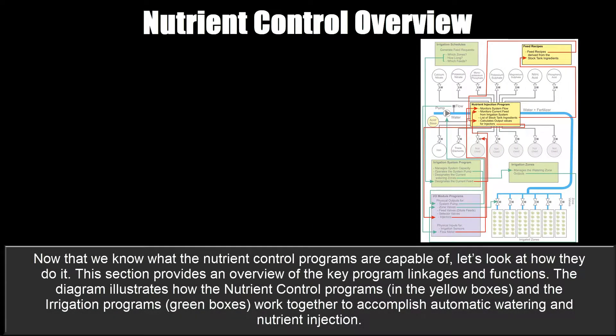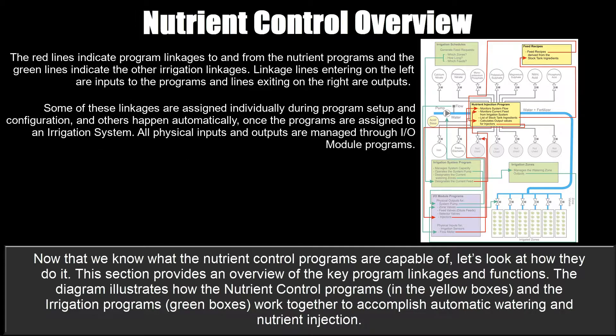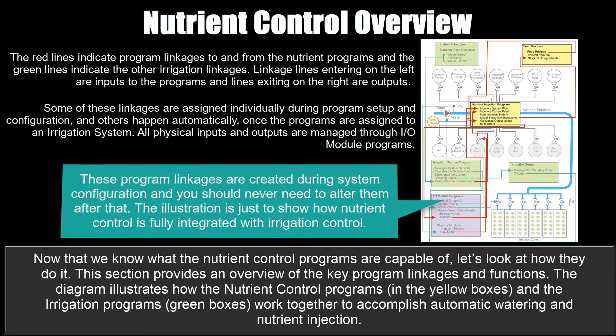Now that we know what the nutrient control programs are capable of, let's look at how they do it. This section provides an overview of the key program linkages and functions. The diagram illustrates how the nutrient control programs — shown in yellow boxes — and the irrigation programs — shown in green boxes — work together for automatic watering and nutrient injection. Red lines indicate program linkages to and from the nutrient programs; green lines indicate other irrigation linkages. Linkage lines entering from the left are inputs and lines exiting on the right are outputs. Some linkages are assigned individually during program setup, while others happen automatically once programs are assigned to an irrigation system. All physical inputs and outputs are managed through IO module programs, with linkages created during system configuration.